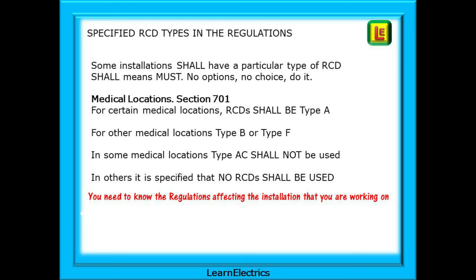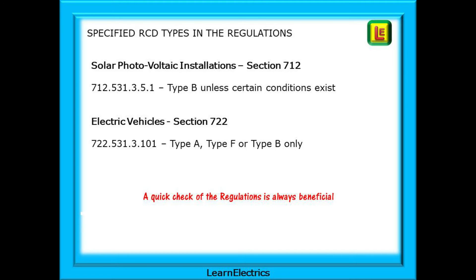You need to know the regulations that affect the installation you are working on. Take a look at solar photovoltaic installations — section 712 and regulation 712.531.3.5.1 specifies a type B RCD unless certain conditions exist. And then we have electric vehicles, section 722, where regulation 722.531.3.101 tells us that type A, type F or type B are the only RCD types to use. A quick check of the regulations is always beneficial.